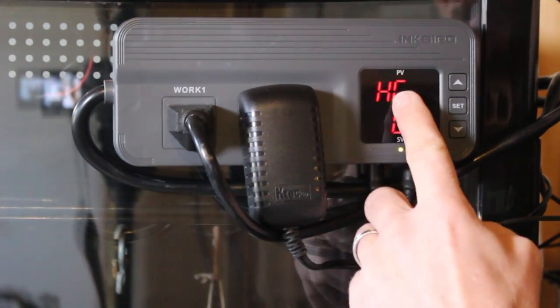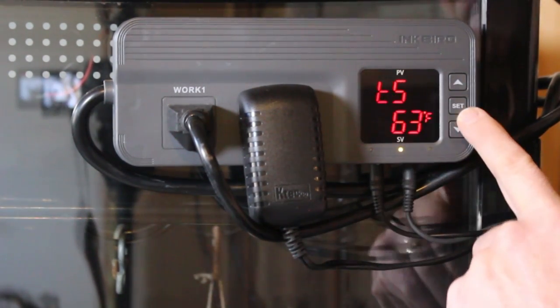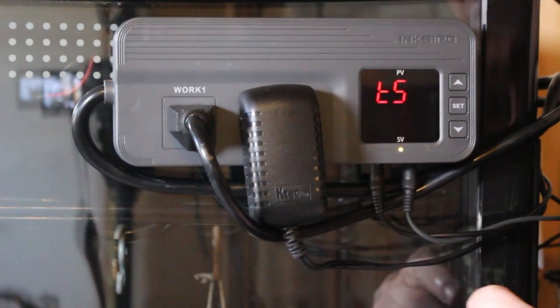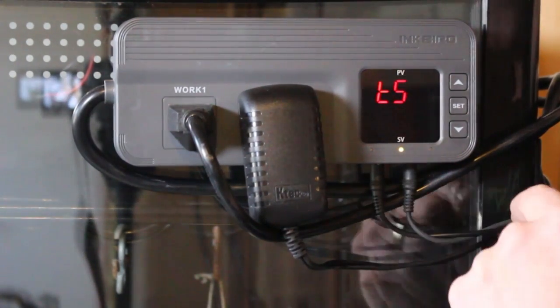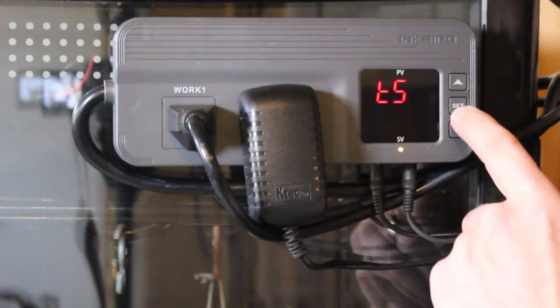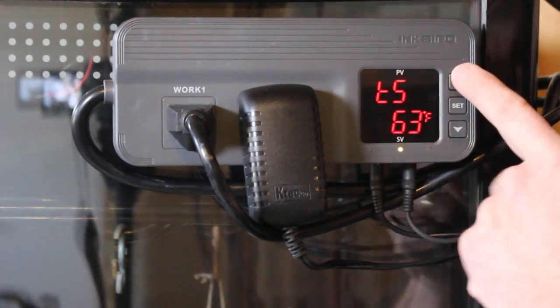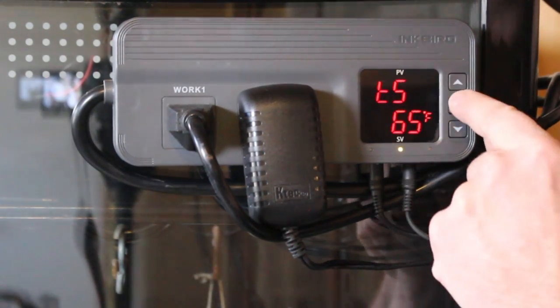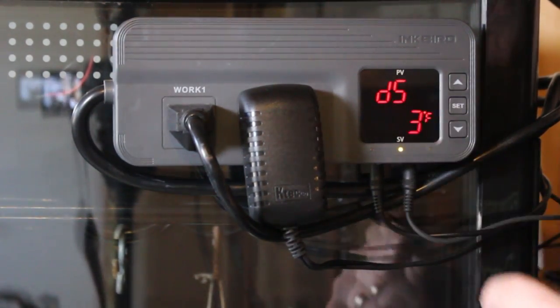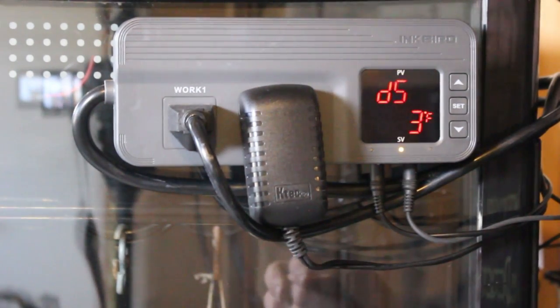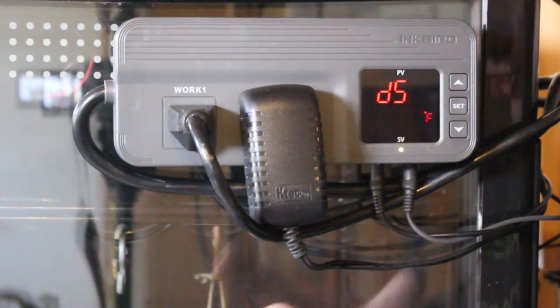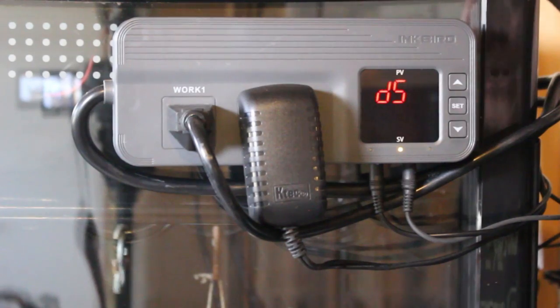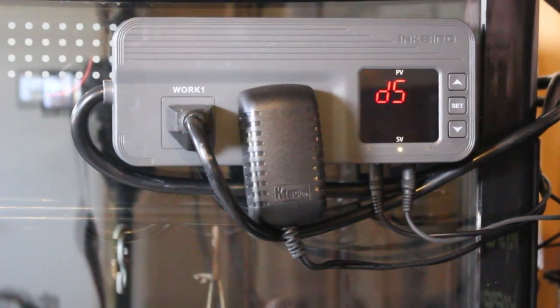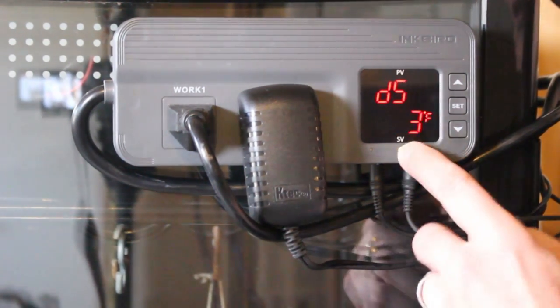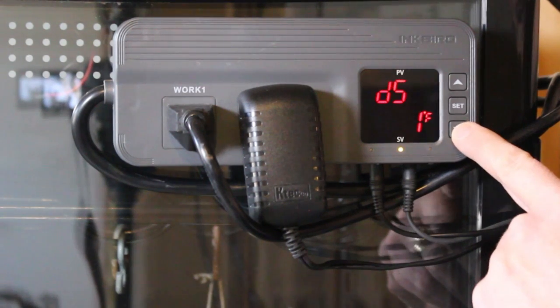So we'll hit set to move to the next setting. Are we heating or cooling? We'll be cooling. Temperature setting, 63 degrees. We just set that a second ago. There you can see we've confirmed, yes, it's set to 63 degrees. And of course, with any one of these settings, you can change it with the arrows. Set. DS is the differential setting. Now, as you're controlling something that's a sophisticated piece of equipment, a refrigerator compressor, you don't want this thing set to 0.